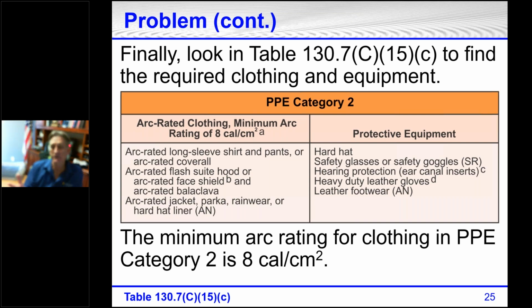This is important, and until last year or a couple of years ago, I always thought that the outer layer had to also be equal to or above the incident energy of your equipment where you're working. It has to be arc rated, but it doesn't have to be that high. So say there's an arc rating of 6 calories on the equipment label. Maybe you're wearing a daily wear shirt that is 8.7 and your pants are 12, and you have to wear a high-vis vest because of where you're working. Well, the vest doesn't have to be 6 calories. It doesn't have to be 8.7. It has to be arc rated, but it's not going to have to be that high of an arc rating.